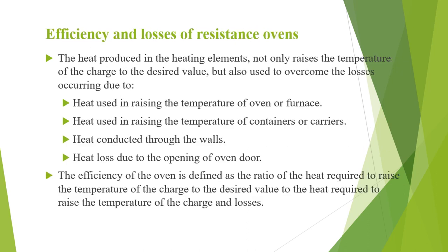Efficiency and losses of resistance ovens: the heat produced in the heating element not only raises the temperature of the charge to the desired value, but also overcomes losses due to: heat used in raising the temperature of the oven or furnace, heat used in raising the temperature of containers or carriers, heat conducted through the walls, and heat loss due to opening of the oven door.